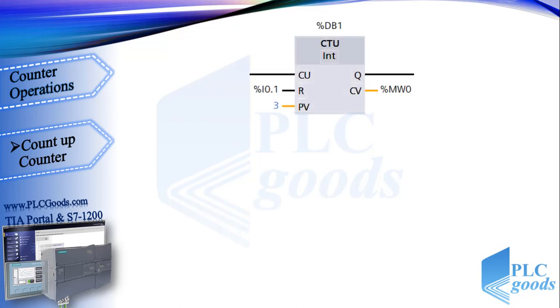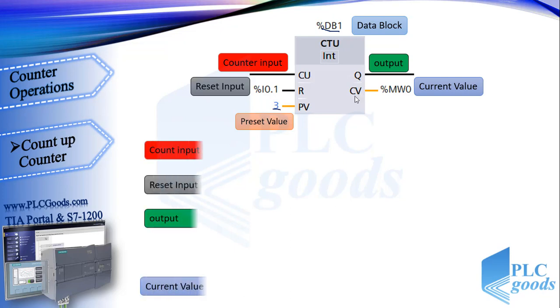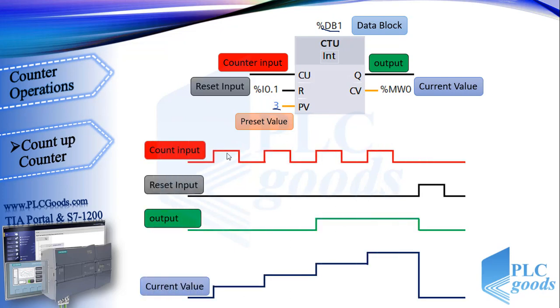Let's start with the count up counter. This is its ladder symbol. This instruction has some inputs and outputs. Like timers, counters need a data block to work correctly. This instruction counts up by 1 when the value of the counter input CU changes from 0 to 1. Similar to timers, here we have reset and preset value terminals. Suppose the preset value is 3.